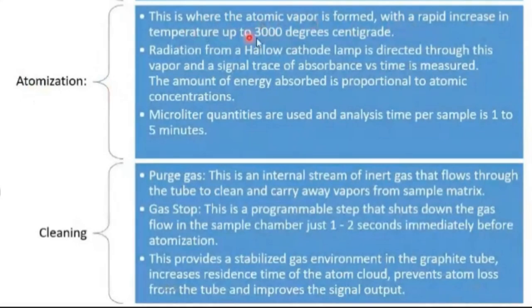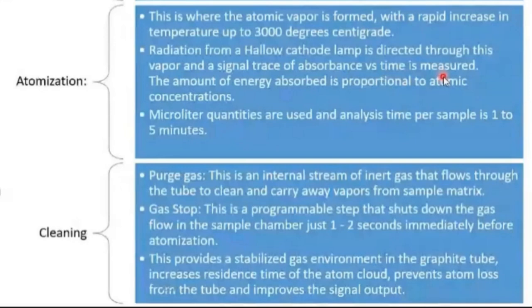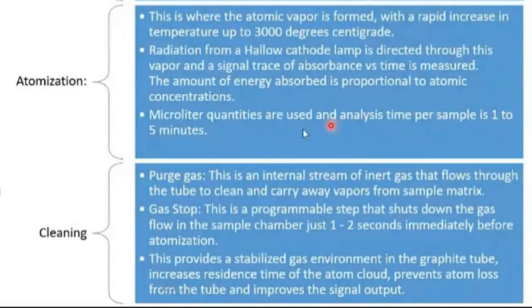Then comes atomization — formation of atoms. The atomic vapor is formed with a rapid increase in temperature up to 3000°C. Radiation from a hollow cathode lamp is directed through this atomic vapor, and a signal trace of absorbance versus time is measured. The amount of energy absorbed is proportional to the atomic concentration. Microliter quantities are used; analysis time per sample is one to five minutes.